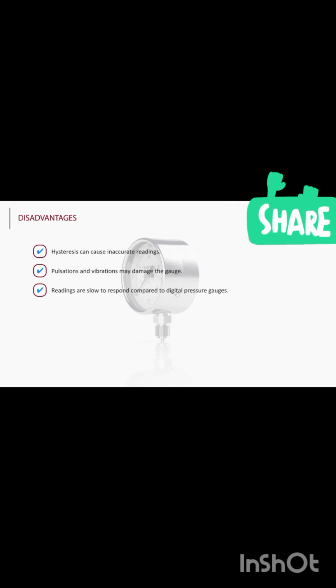The disadvantages of a Bourdon pressure gauge are hysteresis can cause inaccurate readings. Pulsations and vibrations may damage the gauge. Readings are slow to respond compared to digital pressure gauges. An amplification mechanism is required to increase the free end of the movement.